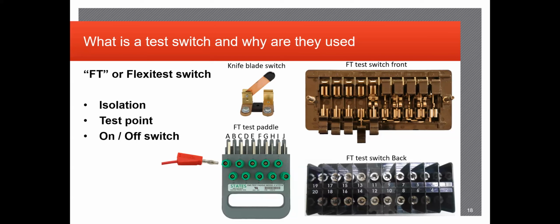They do offer other forms of isolation, whether they be stuff like slide links, but you're not seeing much of those anymore, because they're not super reliable, and can actually lead to injury sometimes if not isolated properly. For example, if you're using a non-insulated screwdriver to open up a slide link that has current running through it and it has power on it, if you mess up even just a fraction, you could short circuit the whole thing and cause injury, damage to the equipment, stuff like that. So primarily you'll probably just see FTs for isolation stuff, as well as obvious circuit breakers, stuff like that.